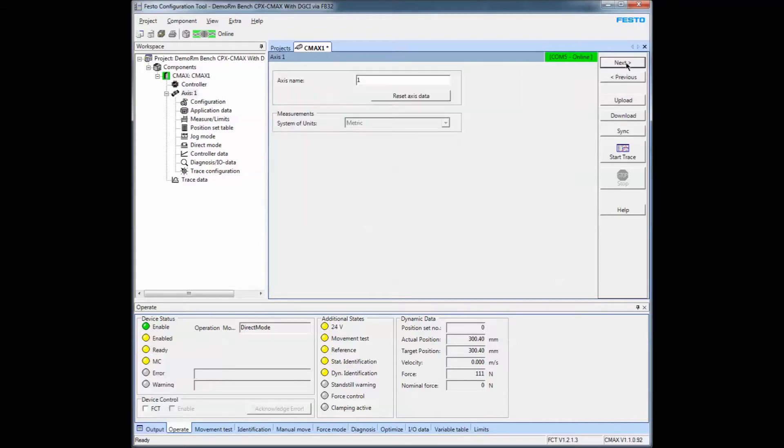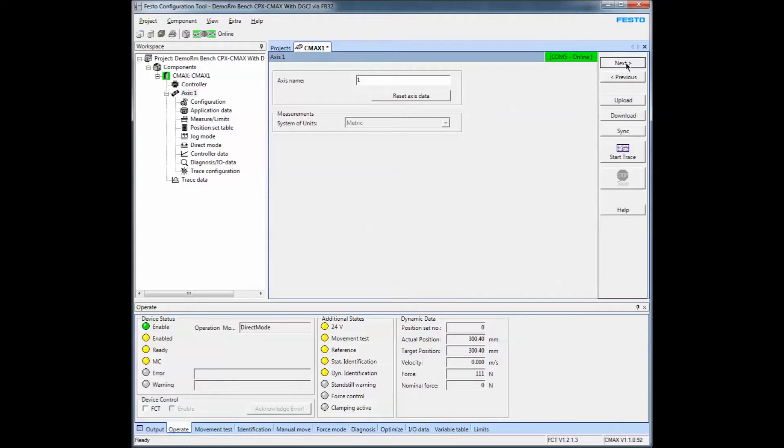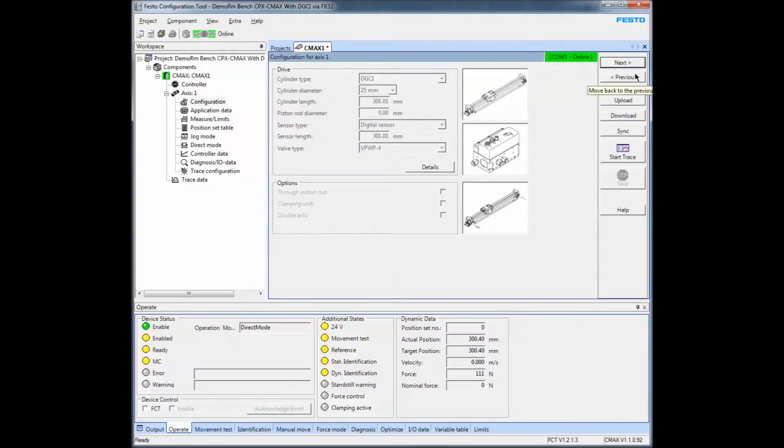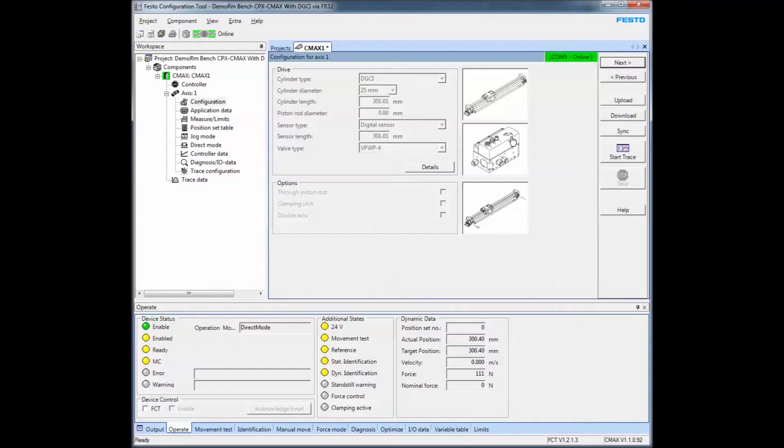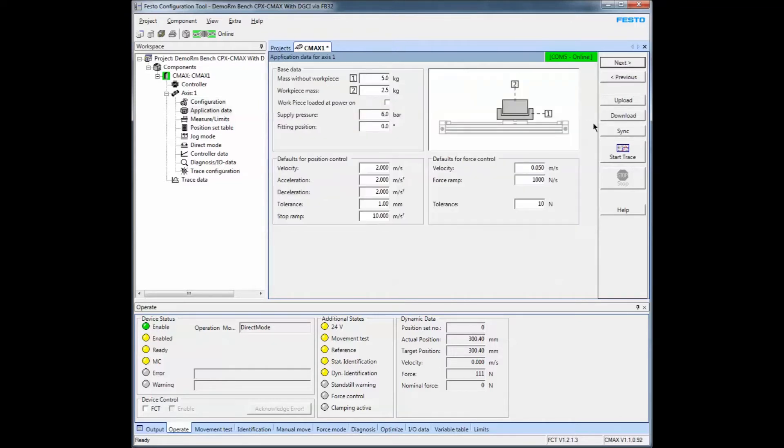This is my system right here, this is my own setup. This is what it sensed. It says it's a 300 millimeter stroke, but in fact it determines it to be a little bit longer and determines the valve size and so forth.